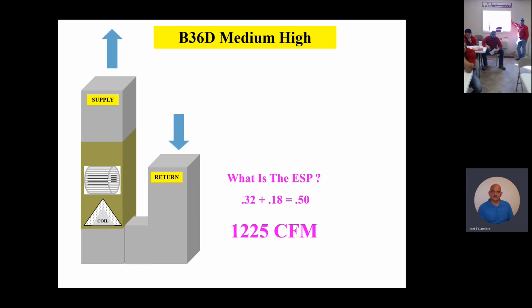So this is probably a 3-ton air handler. It's probably hooked up to a 3-ton unit outside. So if I'm blowing 1225 CFM on a 3-ton unit, how do you feel about that? Good, that's good. Okay, good. So again, put this in your back pocket. We always want to design our ductwork to provide our 400 CFM per ton. In this example, on a 3-ton unit, we're looking for about 1200 CFM. So we're right in there, right? That's in good shape.